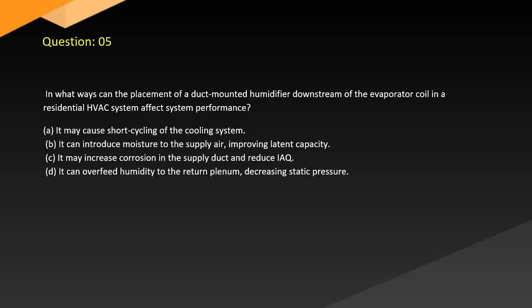Question 5. In what ways can the placement of a duct-mounted humidifier downstream of the evaporator coil in a residential HVAC system affect system performance? A. It may cause short cycling of the cooling system. B. It can introduce moisture to the supply air, improving latent capacity. C. It may increase corrosion in the supply duct and reduce IAQ. D. It can overfeed humidity to the return plenum, decreasing static pressure.